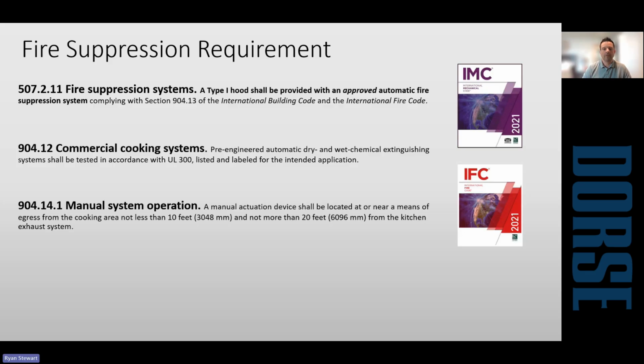They require a manual activation device, so they'll operate automatically off of fusible link or heat detectors in the hood, but they also require a manual activation device. They want it not less than 10 feet from the hood, no more than 20 feet from the hood, and they like to see it in the path of egress. So if you have a fire under the hood, as you exit the kitchen, if the system hasn't automatically activated, you can pull the pull station and manually activate it.